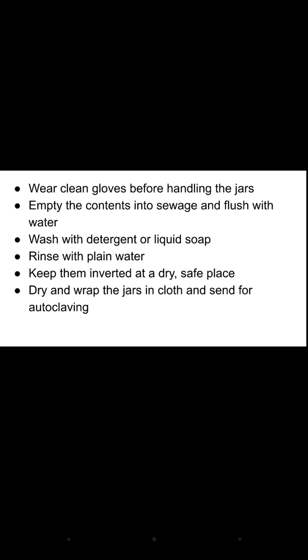You can also wrap the jars in cloth and send them for autoclaving. For the tubes, disconnect them and immerse in a sodium hypochlorite solution for only 10 minutes, then flush the tubing in soapy water, rinse with plain water, wipe the cords with a dry clean cloth, and for the wheels use oil or grease so that the wheels remain active and there is no iron deposition on the wheel.